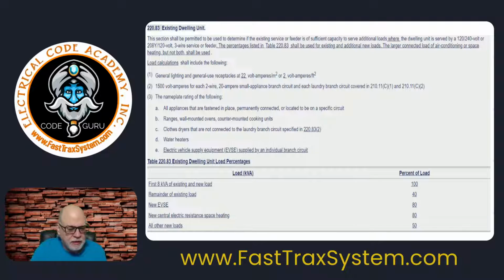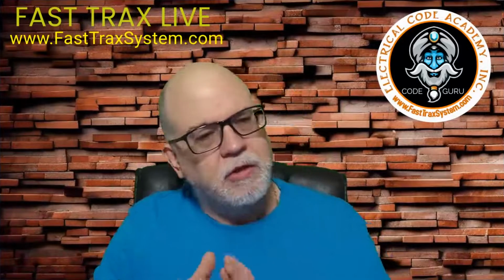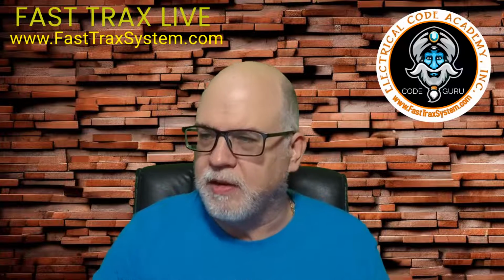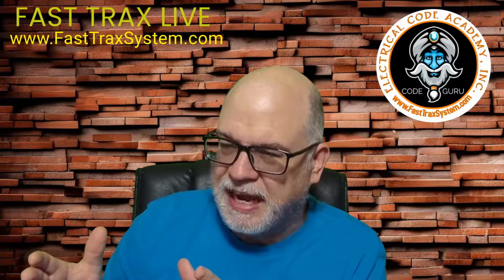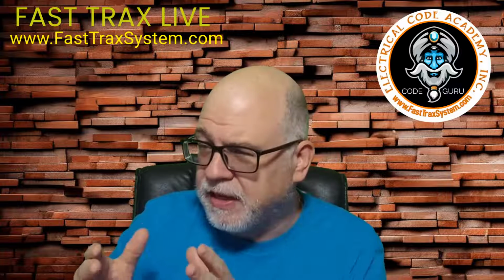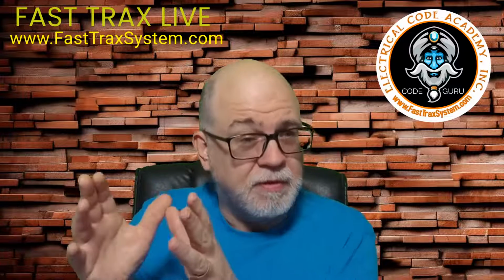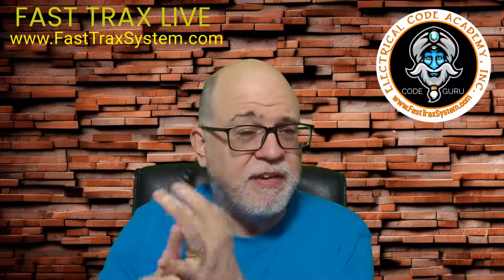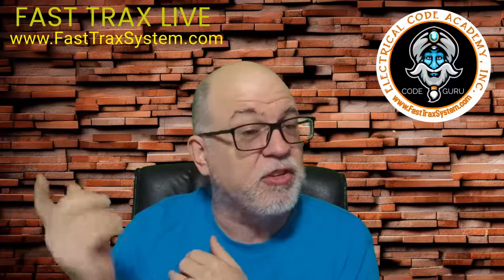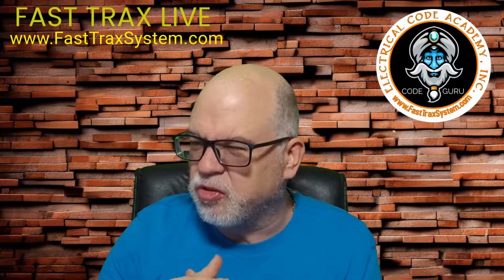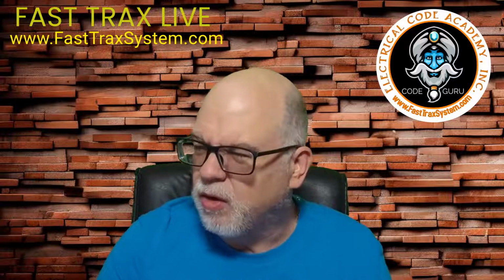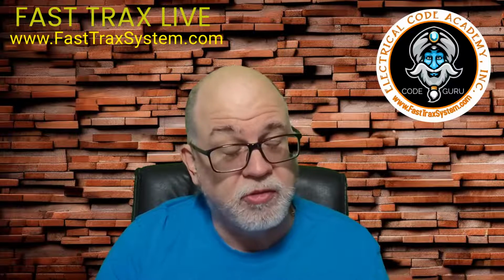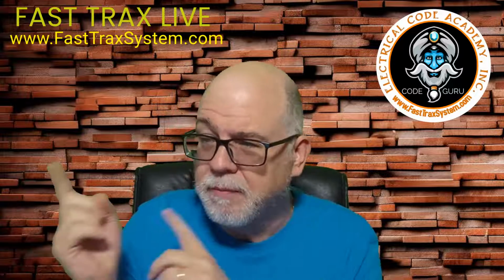So what we're doing here is simply giving you the ability to, in the 2026, we're going to say, okay, well, I have all of my existing loads. That's the first part. Then that's the part that I'm going to apply to the first 8,000 at 100%. And then the remainder over that at 40, that's existing. And then if I've got any new EVSE, I'm going to take it at 80% and add it to that number. If I've got any new central electric space heating, I'm going to take that at 80%, add it to my total. Or if I have any other new loads, whatever they may be, at their nameplate, boom, I'm going to add it to what?